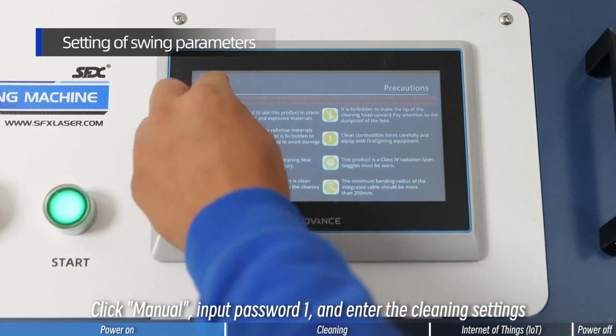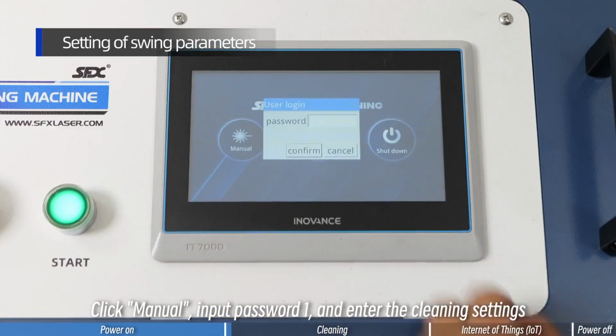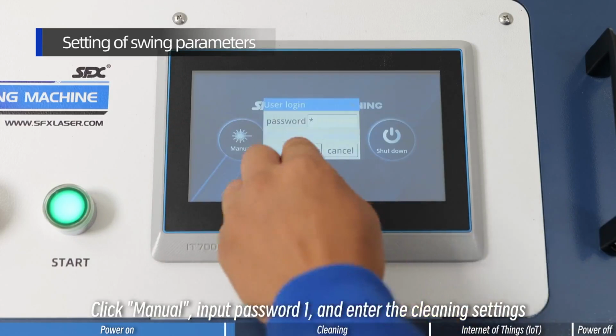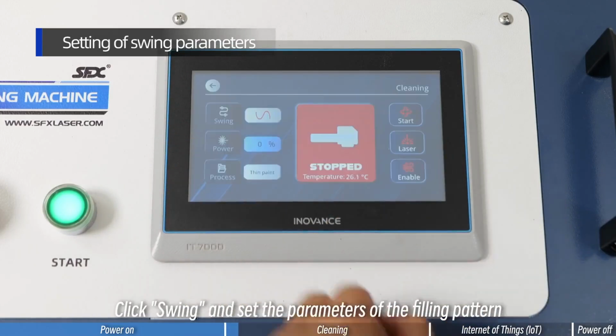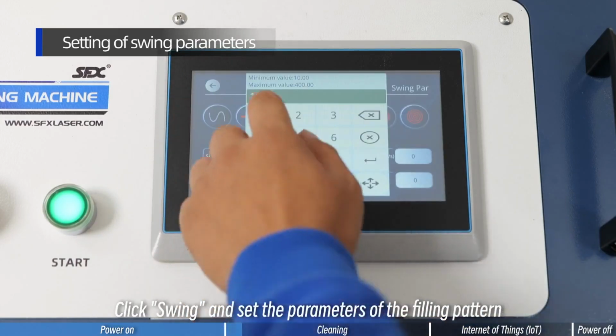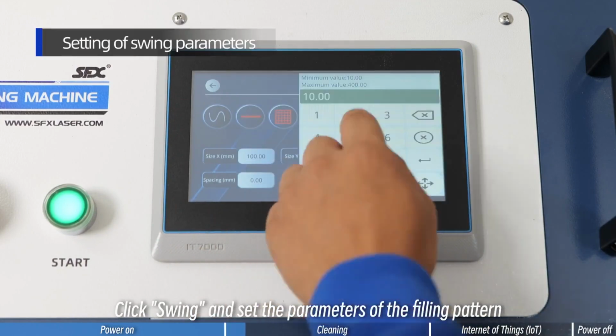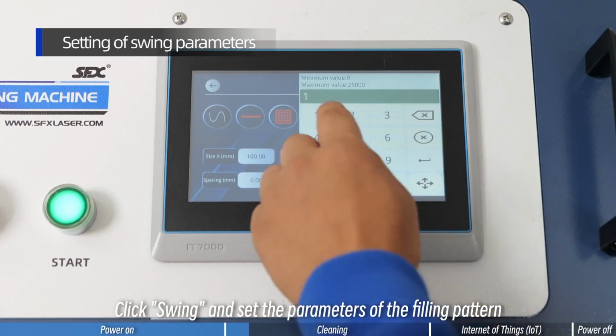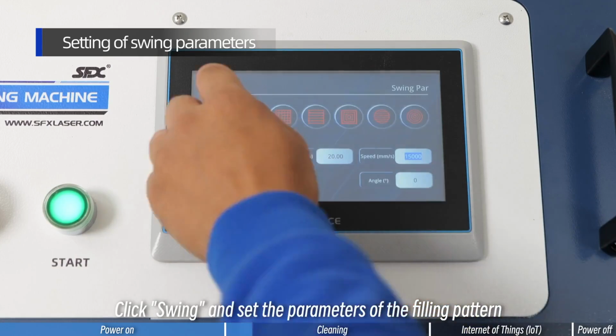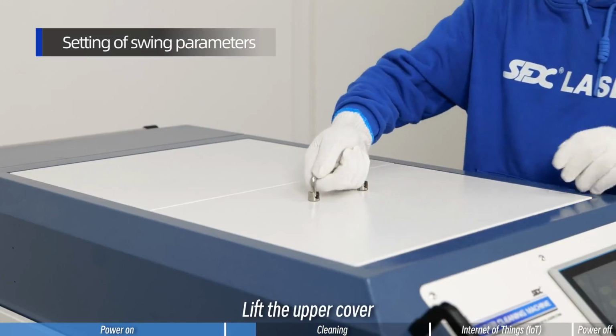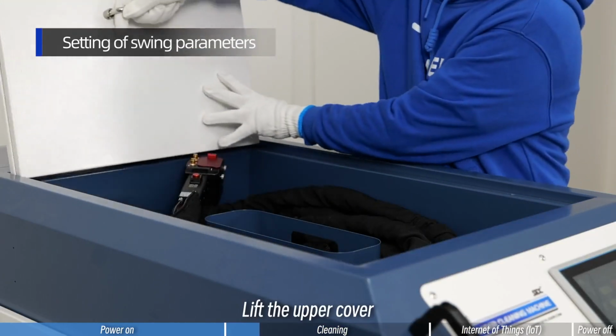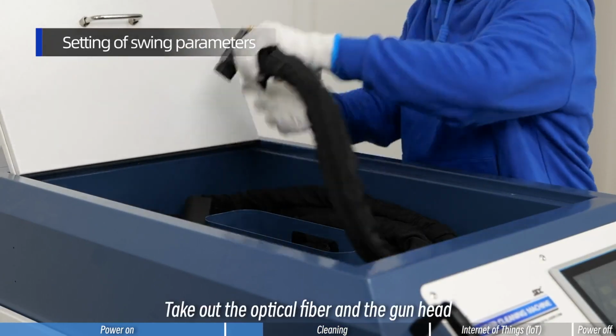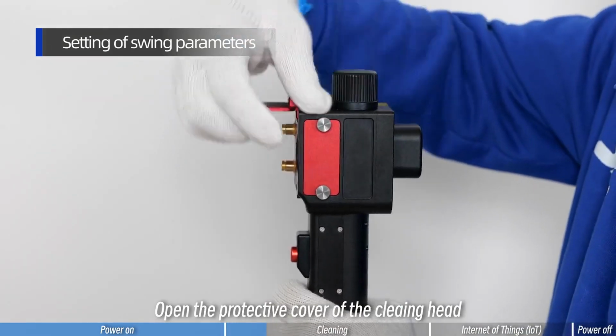Click Manual, input password 1, and enter the cleaning settings. Click Swing and set the parameters of the filling pattern. Lift the upper cover. Take out the optical fiber and the gun head. Open the protective cover of the cleaning head.